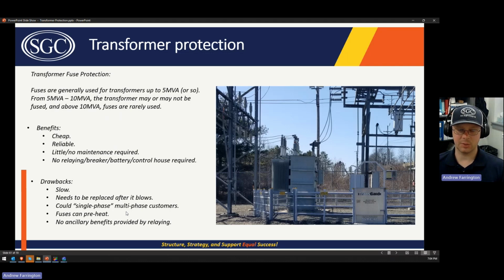We talked about that during the Aspen One-Liner course. I think I just touched on it, but basically, if you have three phase customers on the low side of the transformer, you have a single line to ground fault. I go through an example of this, I think. I'll save it for when I go through the example. The fuses can preheat. We talked about that. You have different K factors that you need to account for due to the preheating of the fuse.